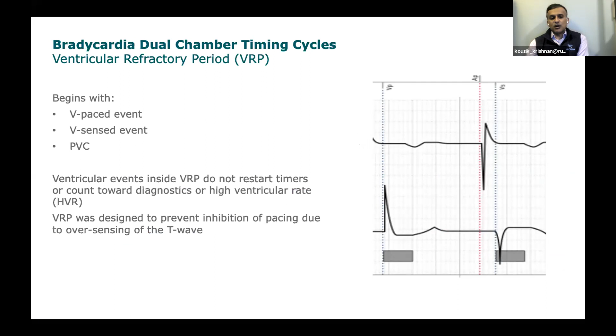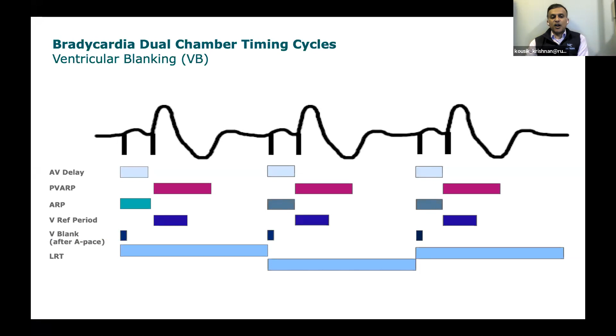I know it gets a little complicated here because I'm drawing in all these different timing cycles that are happening, some of which are more important than others to understand, such as the AV delay, the PVARP, the ventricular refractory period, and the lower rate timer. But it's important to understand these things or know that they exist, because sometimes that is the reason why your device will have function that may seem like it's malfunctioning when it's really not. It just may be something inherent to a blanking period that you may need to adjust in order to make the device work properly.